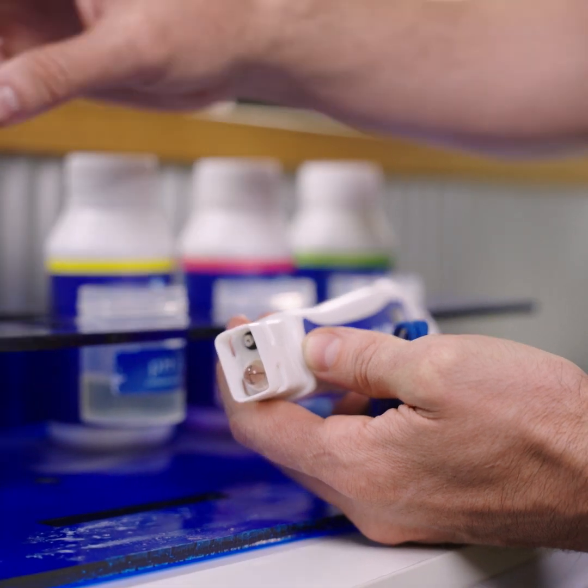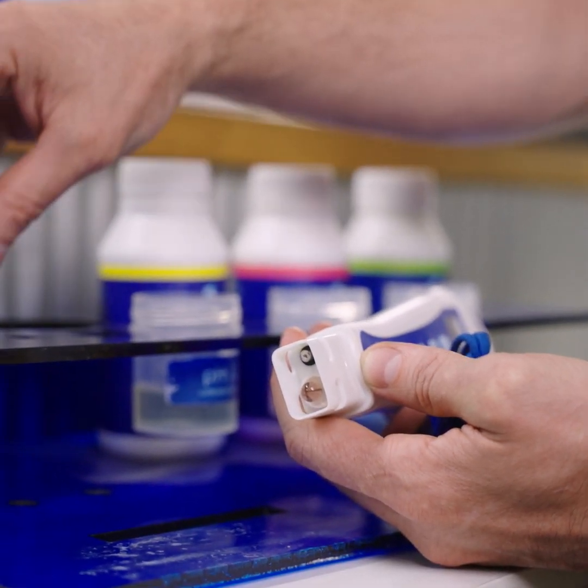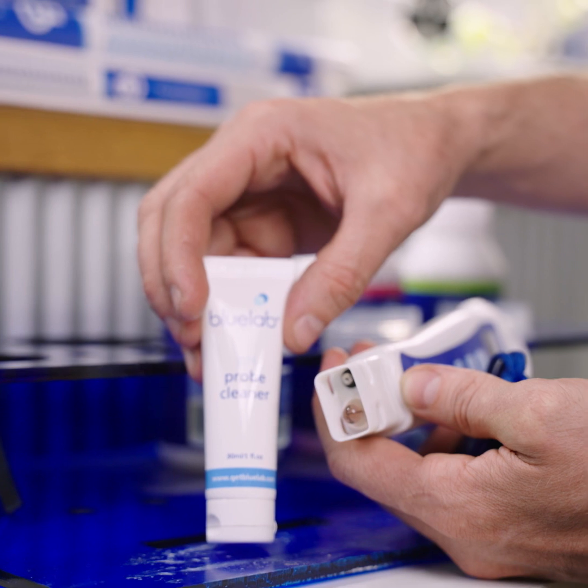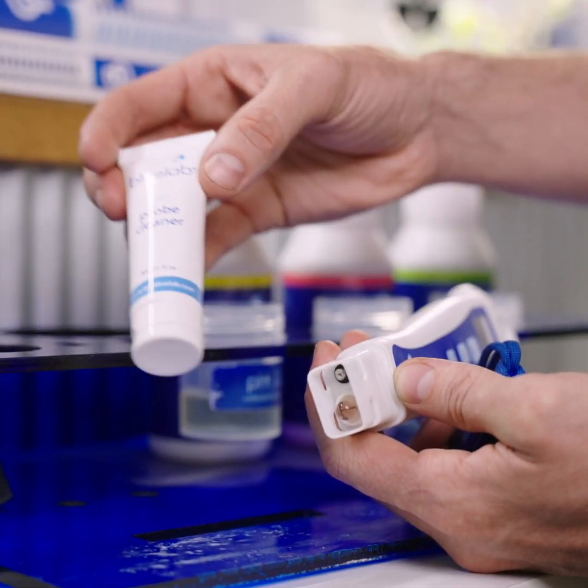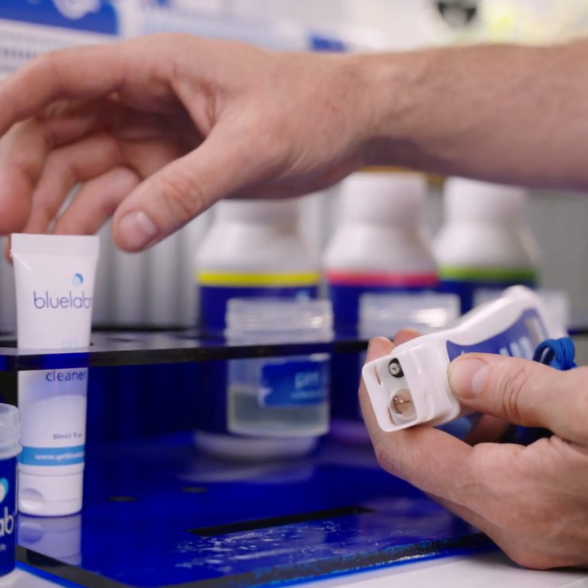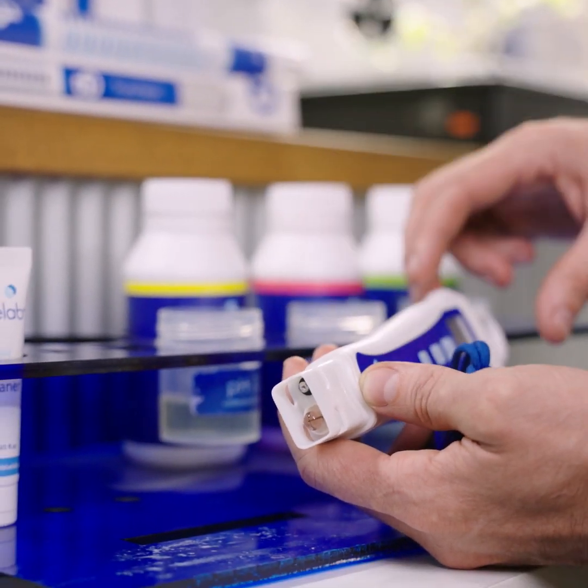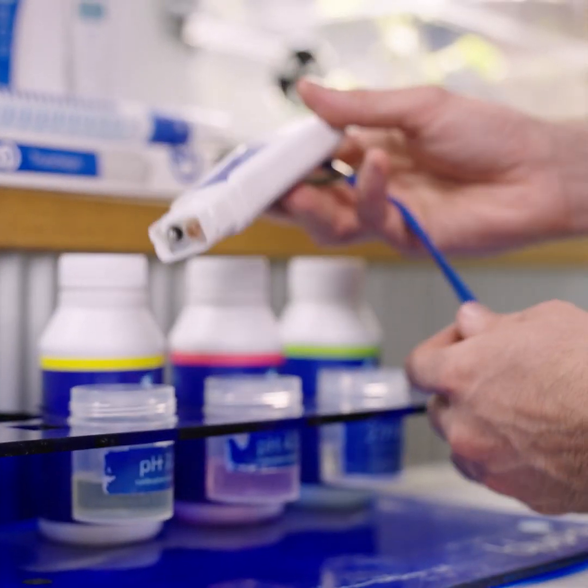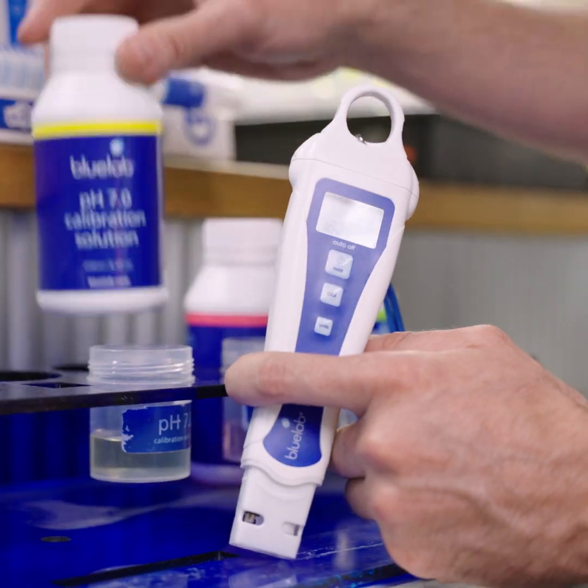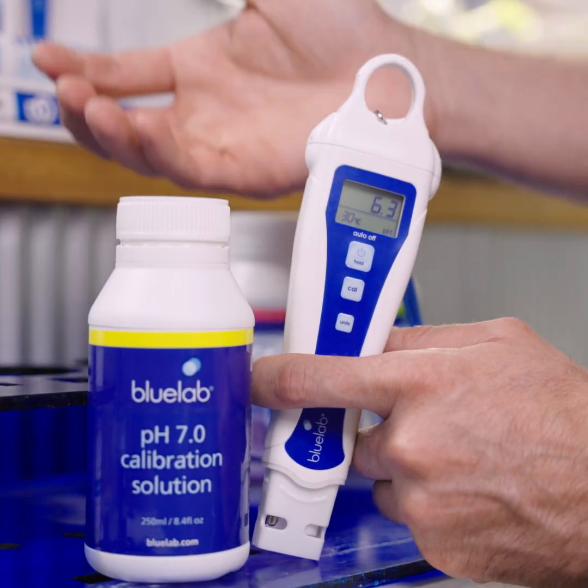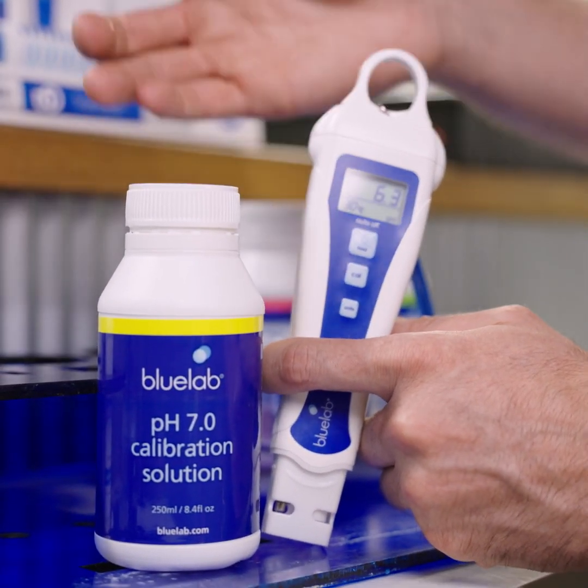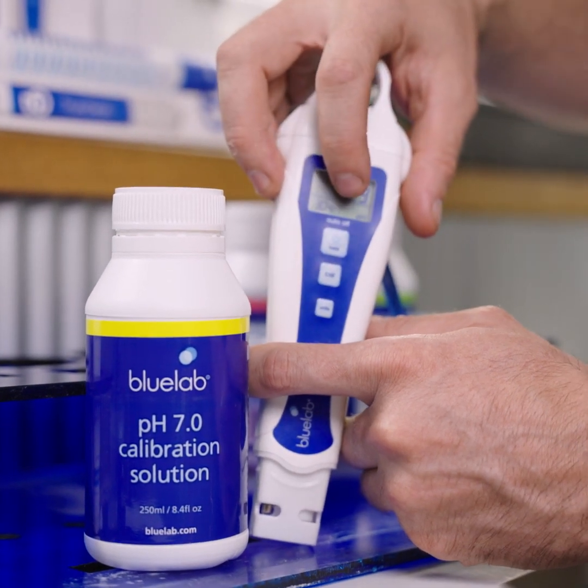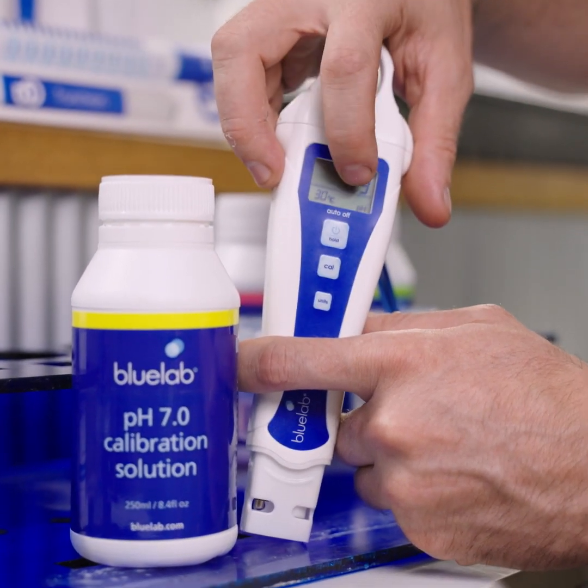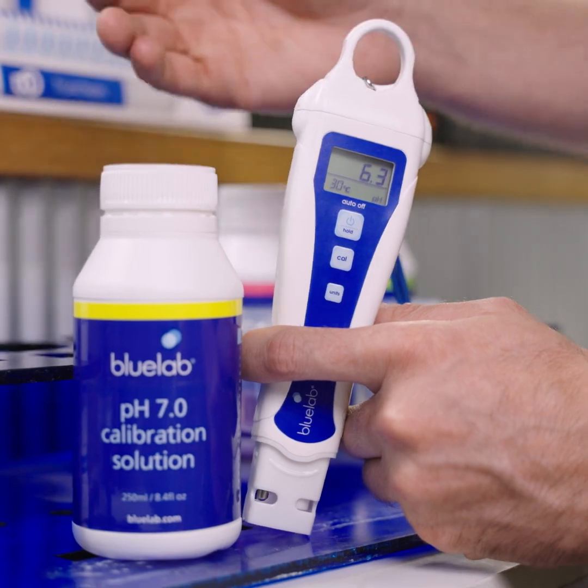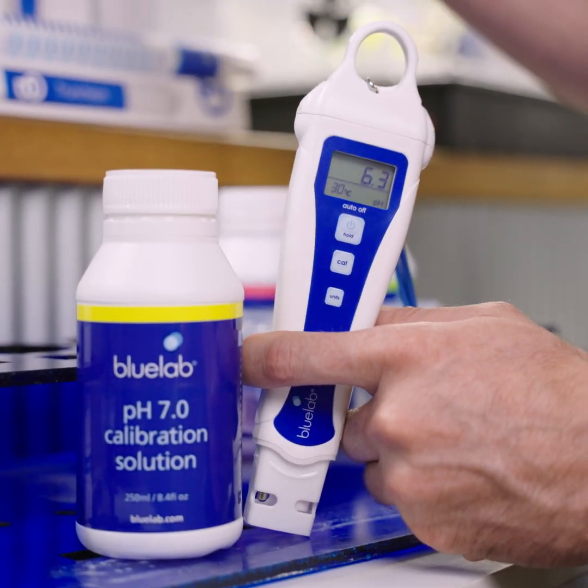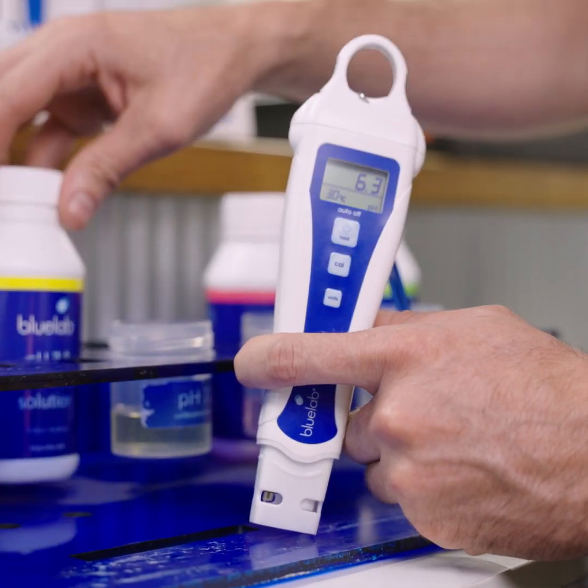And if you get a cleaning kit, a probe care kit, you'll get a little bit of probe detergent. You'll get a brush, and you'll get some storage solution. So we'll go through that in a second. But to calibrate, you always want to go to your pH 7 first. A lot of people come in saying there's an error, that their pen's not calibrating. It'll come up with a little ER on the screen. That's because they've gone for 4 before they've done 7. So you want to do 7 first.